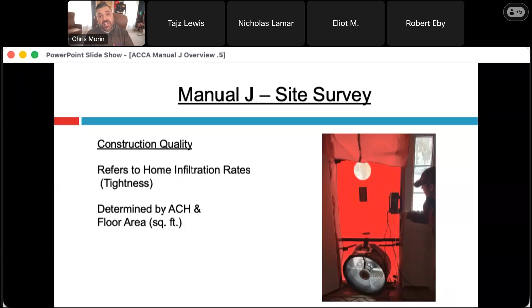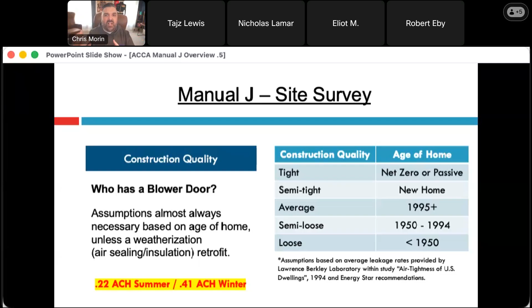So for Austin, standard construction homes are typically going to be set for semi-tight. And that's because you have a target of 0.22 air changes per hour in the summer, and 0.41, which is accommodating higher wind, air changes per hour in the winter. If you're going to use a net zero house or more extreme construction, you're going to be setting your construction quality to tight. If you have a target ACH, you can just enter that though, right? Keep in mind, for existing homes that are going to be weatherized, it can drastically change a loose house all the way up to average if you weatherize a home that isn't tight enough to require ventilation at that point. So really important, you need to know what you're looking at and what those set points are going to be when you're doing your load calculation.